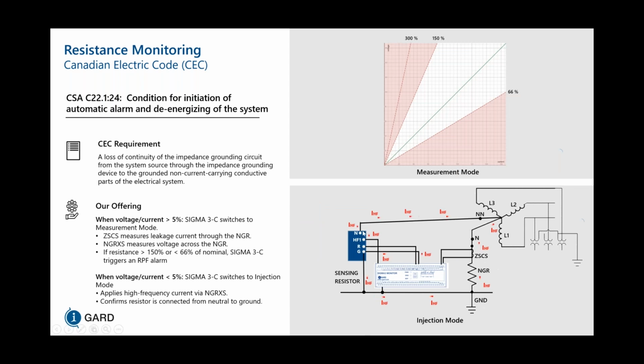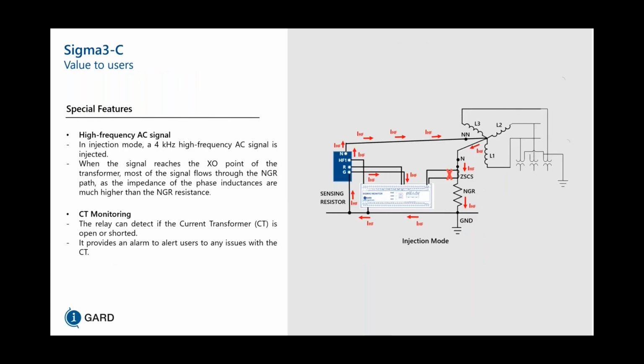Now, when this high frequency AC signal is running through the route of being injected to coming back to our relay, and all of a sudden there's an open circuit which doesn't allow it to come back, then we can indicate that we have now experienced a break in our connection with respect to our high frequency AC signal. In addition to that, if there's a known voltage and current, then we can switch to measurement mode where we use Ohm's law to calculate the resistance and compare that to the nameplate resistance of the NGR. If we're below 66% or above 150% of that rating, then we can indicate an NGR fault in that scenario.